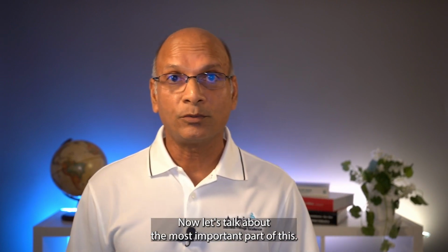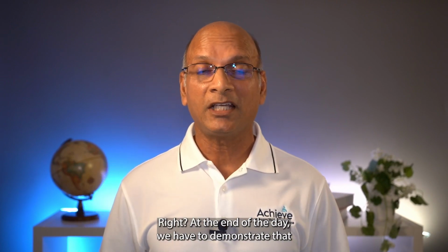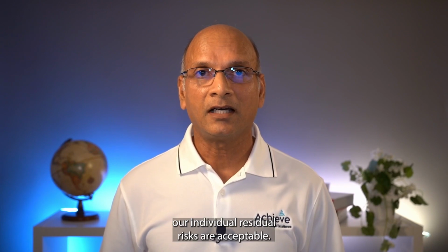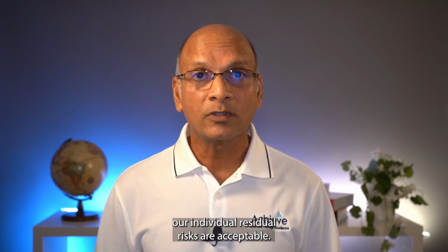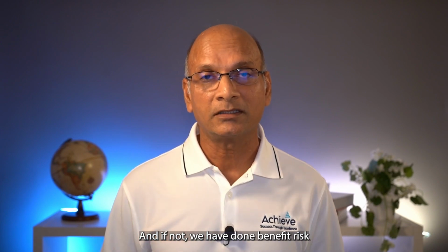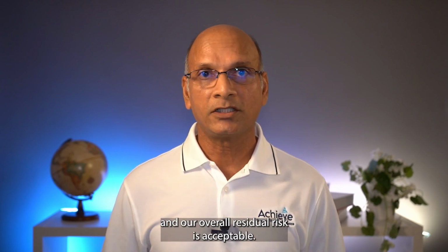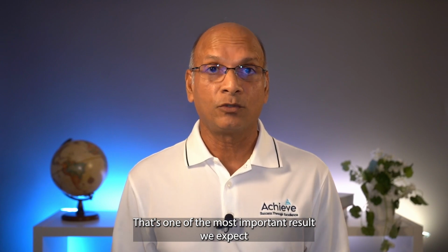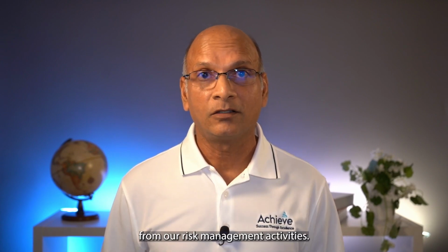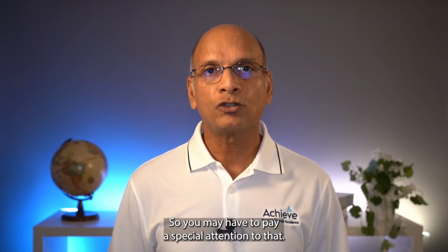Now let's talk about the most important part of this, right? At the end of the day, we have to demonstrate that our individual residual risks are acceptable, and if not, we have done benefit-risk, and our overall residual risk is acceptable, right? That's one of the most important results we expect from our risk management activities. So you may have to pay special attention to that.